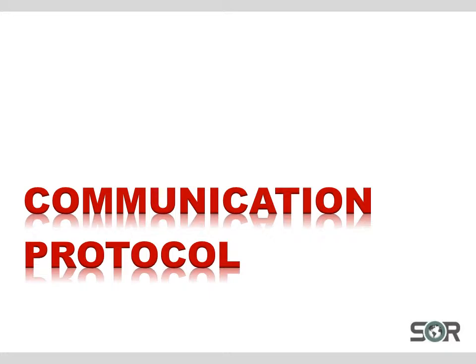The 815 PT offers HART 7 communications protocol and Modbus RTU serial communications. For clarification and increased knowledge, consider the following definitions. HART is an acronym that stands for Highway Addressable Remote Transducer. A HART-enabled instrument like the 815 can send and receive digital information across analog wires to a control or monitoring system. HART communicates at 1200 bits per second over the current loop found in many older plants worldwide. The HART digital signal is superimposed at a low level on the 4 to 20 milliamp analog measurement signal without causing any interference with the analog signal. For more information on HART, go to hartcomm.org.